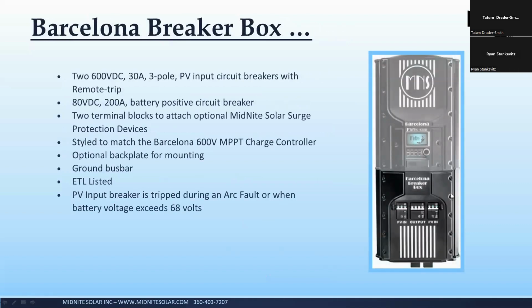The Barcelona Breaker Box, exactly the same thing, just twice as much fun. You've got two 30 amp PV input breakers, one on each side, and your main 200 amp breaker. So very similar. The one difference about the Barcelona, in this picture here, it's a little hard to see, but it does have battery studs hanging out of the bottom of it. So a lot like an inverter, if you don't want to run conduit up into it and you just want to connect to it, there's a 5/16 positive and negative stud on the bottom of it where you can land your battery cables external to the box, because remember, it's 200 amps. You can actually remove two little bus bars internally, and you can conduit into it and run your battery cables internally too if you want to run conduit.